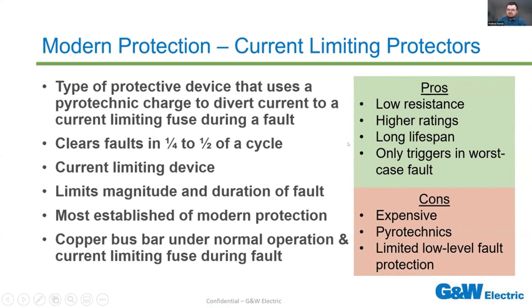And it is a device that operates in backup, so it only triggers in the worst case fault. Unlike something like a fuse or a breaker that can nuisance trip at low level faults, these current limiting protectors are designed to only trigger in response to your worst case, 1 in a million fault scenarios, to try and avoid those nuisance trip scenarios. So the cons: they are expensive. They are a bit more expensive than an equivalent reactor at the same ratings. However, they are much smaller in size.